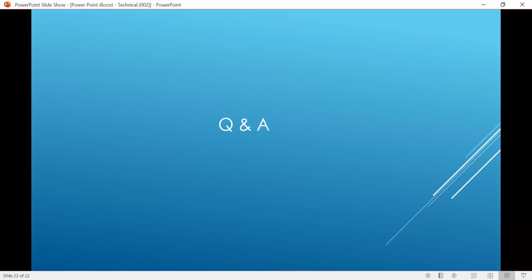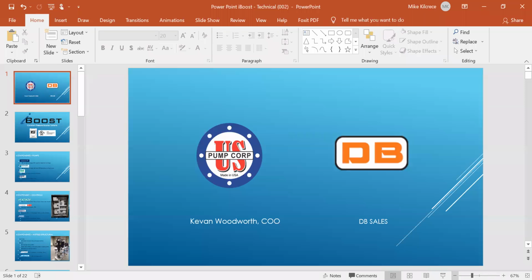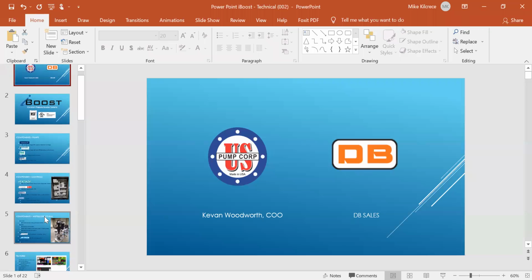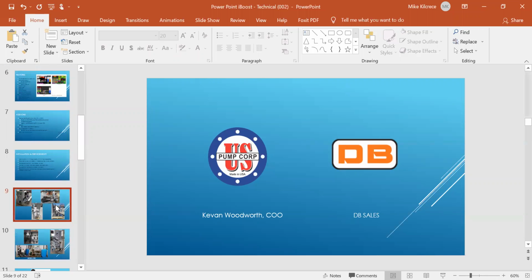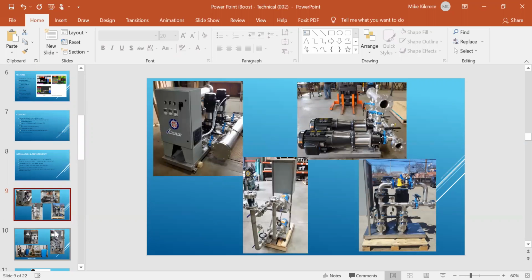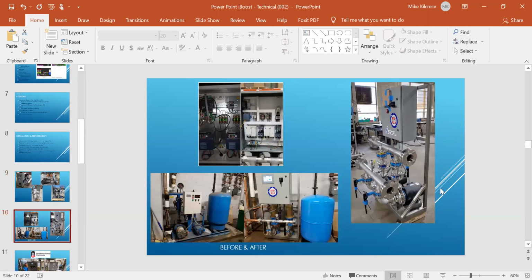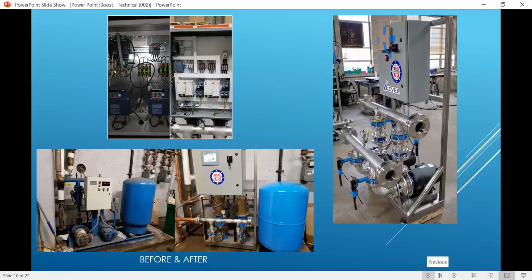A lot of the time what we see on those hydropneumatic tanks is just for ease, it's typically installed right next to the booster, which is on a ground level kind of situation. But there's a pretty easy way to save money when you can, and that's definitely putting that on the top of the building. It kind of uses gravity to add additional boost or take up some of the boost that's required in the building as well. You can also save cost on the size of that hydropneumatic tank, reducing the size and pressure. That's right. In a building, you don't need a high pressure 250, 300 psi. You can go down to a 125. And that's going to be a significant pricing decrease.